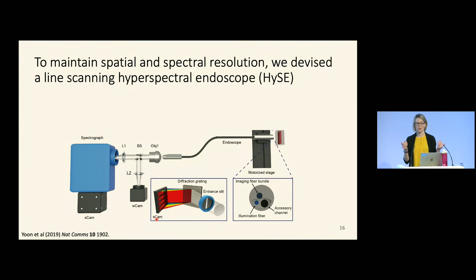That means that in order to build up a full image, I have to scan my endoscope around. But it turns out that's what endoscopists do anyway when they're trying to look for cancer. They look around the esophagus. So that's okay. We then have a white light LED to illuminate the tissue, so we're using the same kind of broadband light source that we normally use. Now, the reason that this works so well is that we have our regular high-resolution image, which allows us to reconstruct the scanned information from the spectral camera.